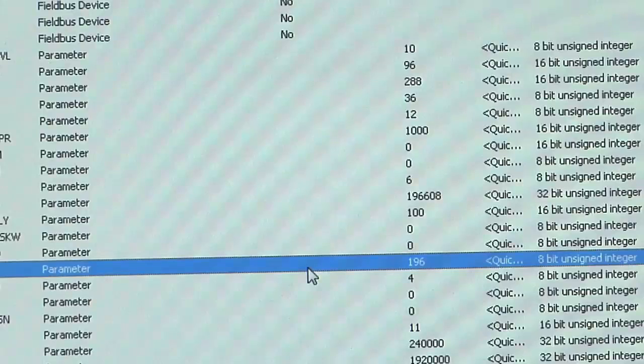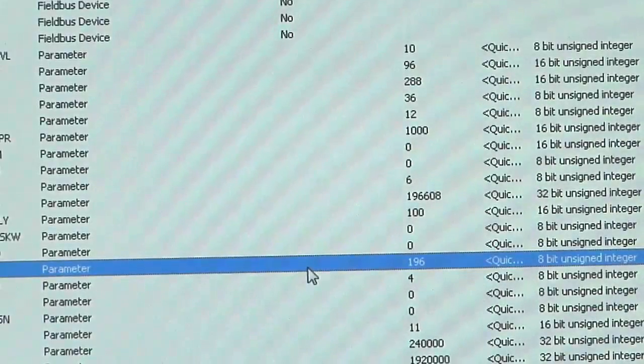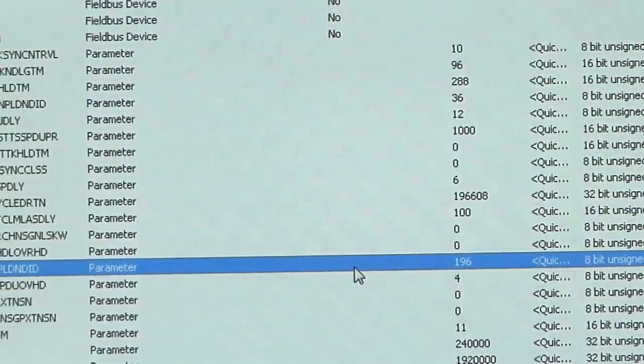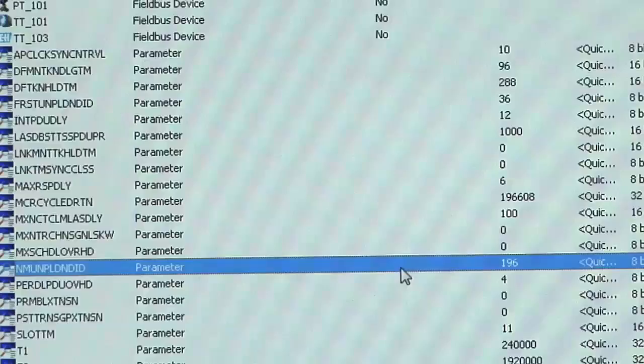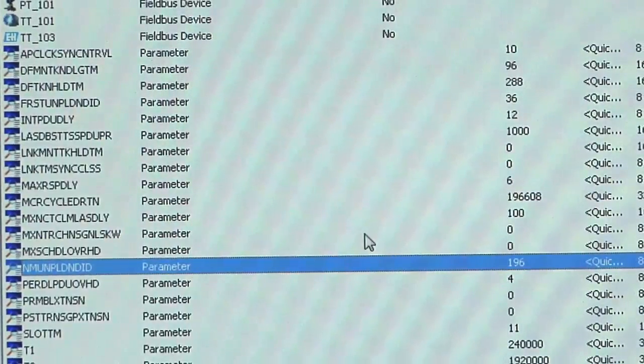So what I do is I go back and I reconnect the device on another host, or in this case on a handheld communicator, another device, and what I've discovered is that the device in fact was addressed for address 39. Now how are we going to fix that? So let's take a look at that for a second.